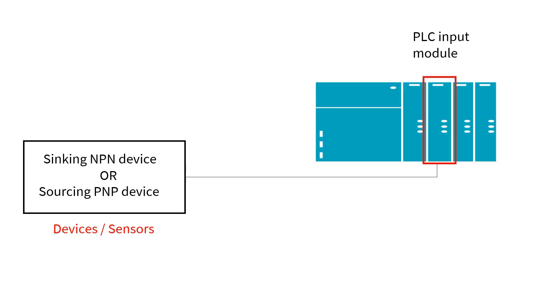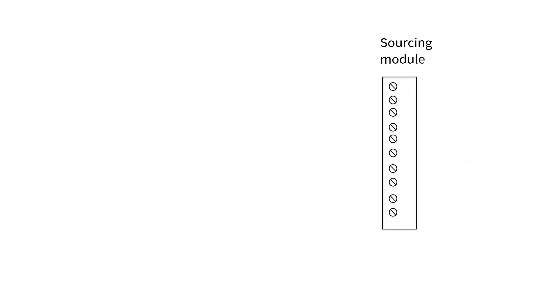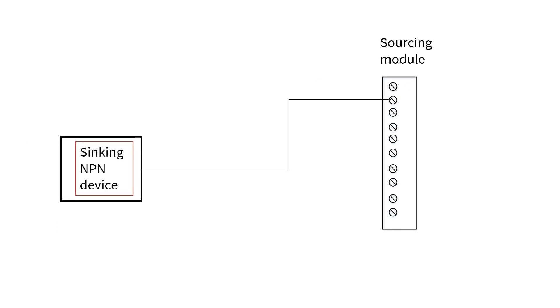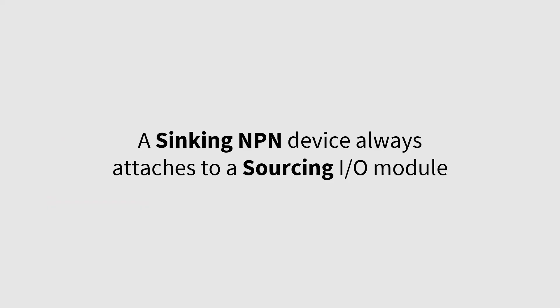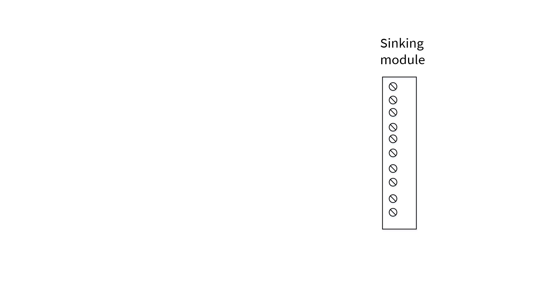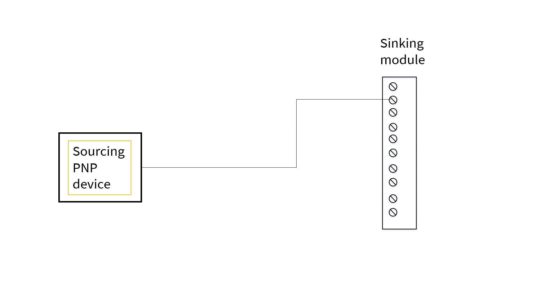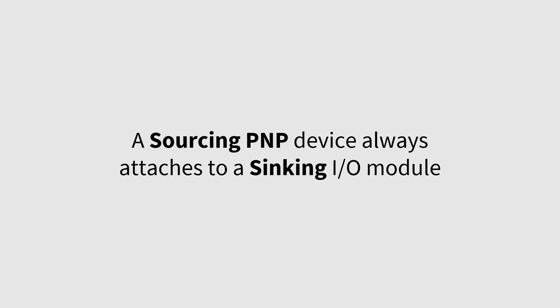The devices connected to the PLC I/O module are also labeled sinking or sourcing. When we have a sourcing module, the device connected to it is a sinking device. In sinking NPN devices, current flows into the device from the module — the module provides or sources the current. A sinking NPN device always attaches to a sourcing I/O module. The same applies for a sinking module: the device connected to it is a sourcing PNP device. In sourcing devices, the current flows out of the device into the module — the module receives or sinks the current. A sourcing PNP device always attaches to a sinking I/O module.